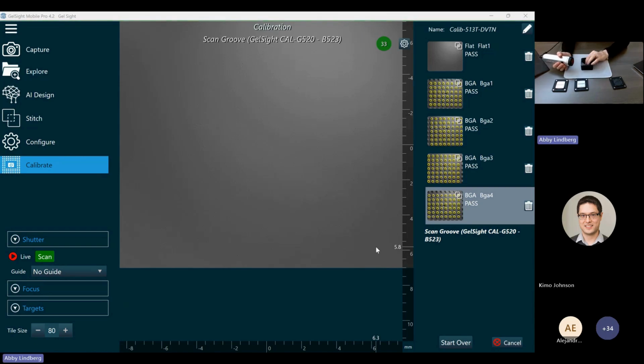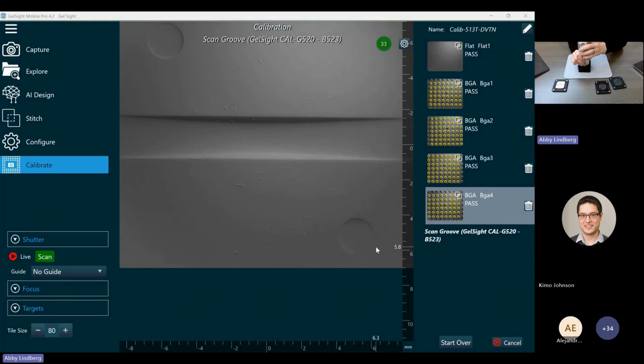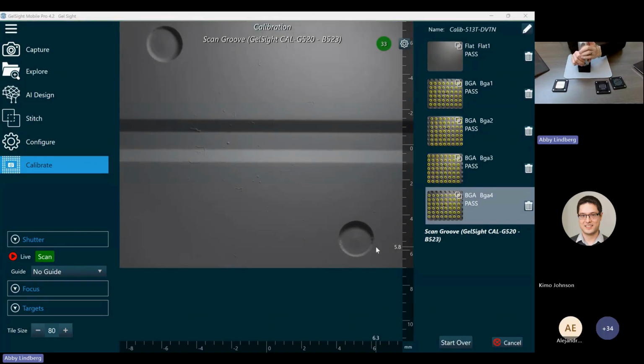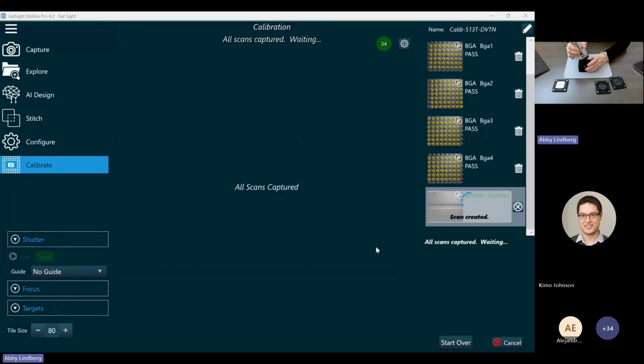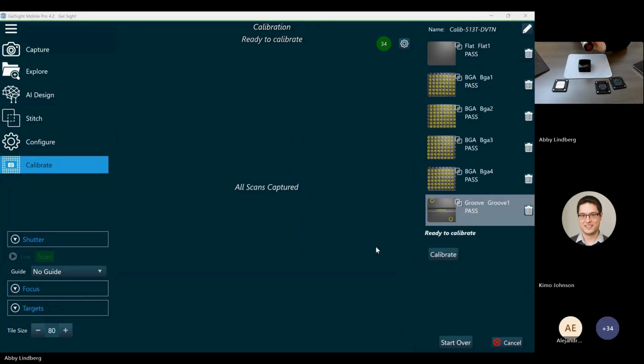And finally, it says scan groove. So we're going to switch over to our last scan for the calibration process, which is our groove target. We'll snap that fixture onto it like that, and we're ready to take that scan. For this one, we just need to make sure we're seeing both holes in the bottom of that groove. And we'll click the button to take that scan. And once all of our scans are taken, we can click the calibrate button.